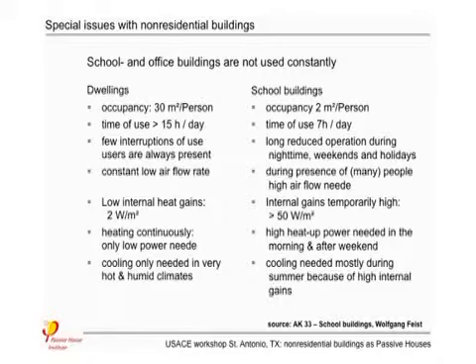Here you have a constant airflow rate. Here, when many people are there, you have a very high airflow, and afterwards no airflow or very low airflow. Internal gains are 2 watt per square meter here, and when people are there, up to 50 watt per square meter. Or if you start in the morning, coming from the weekend, you have to preheat the rooms for 1 hour, and therefore you need some high airflow and high power. Here, heating continuously means only low power all the time, and here, heating in the morning and not then. And the same with cooling.